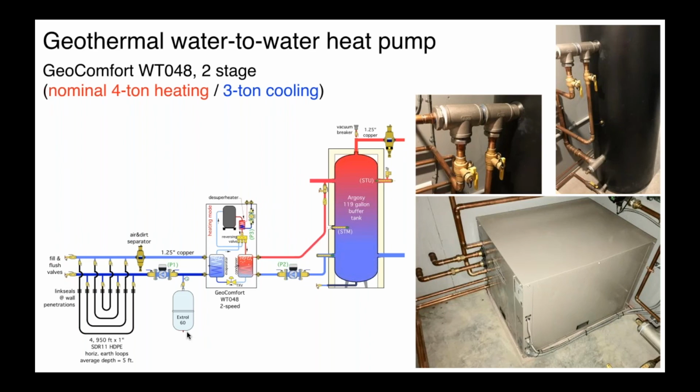One of the things you will find with a geothermal loop, and you would also find this with a solar thermal collector system operating with antifreeze, is that you fill the loop up at maybe 55 or 60 degree fluid temperature. There are going to be times when that temperature actually gets colder than that. I did the math on this, and it actually isn't a big effect. What I would suggest is to pump a little bit more fluid into it. If your static pressure is nominally going to be, let's say, 12 psi, you might pump the tank up to 14 or 15 psi. You're pushing a little extra fluid into that tank so that when the loop is at its coldest, you're not going to cause the diaphragm to be fully expanded against the shell of the tank.